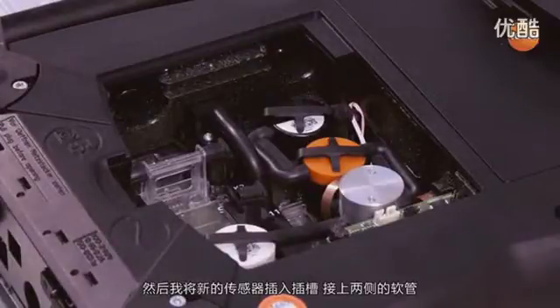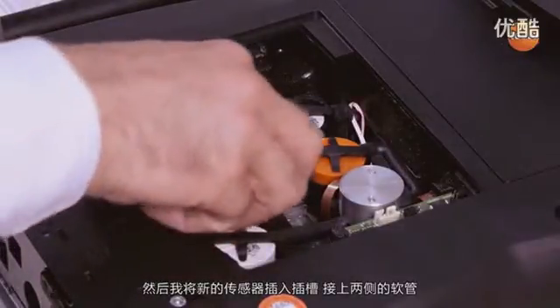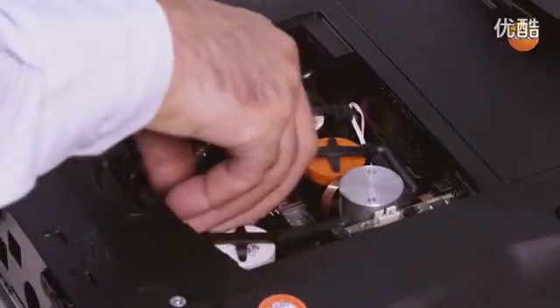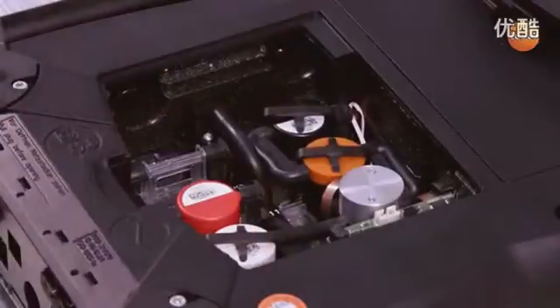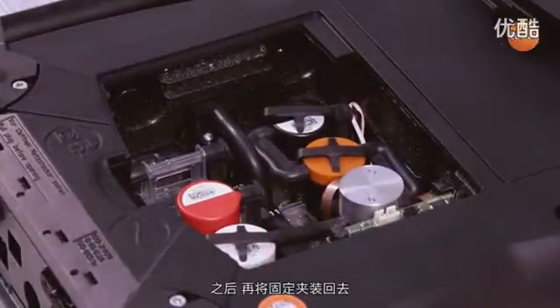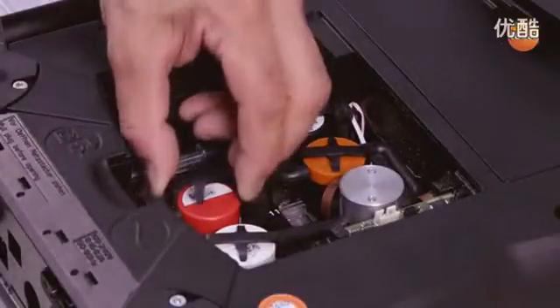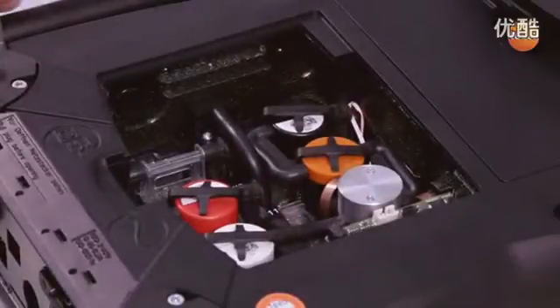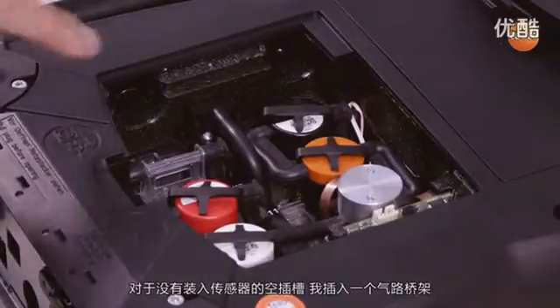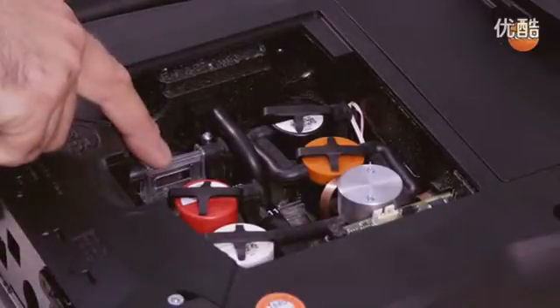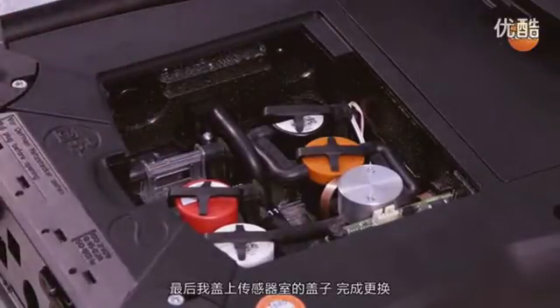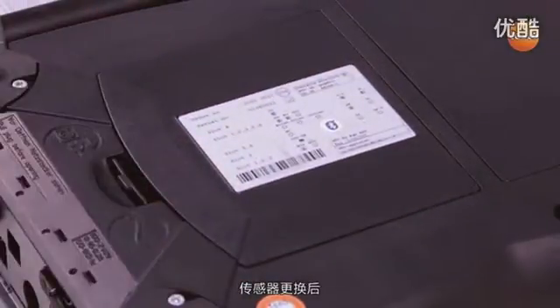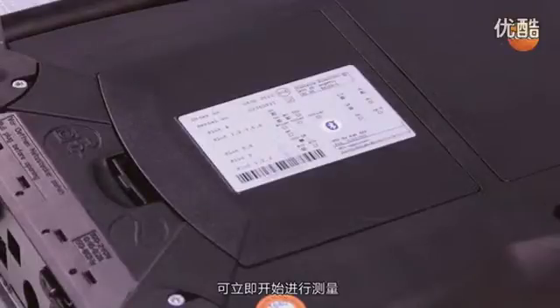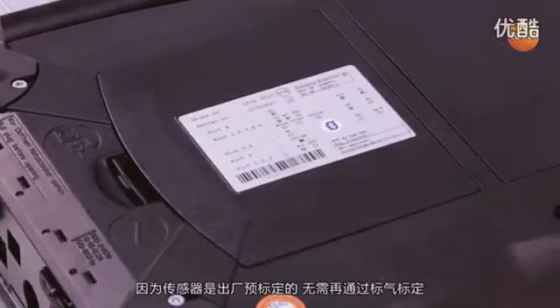I then insert the new sensor into the slot and connect the sensor to the hoses. After this, I click the clip back into place. I insert a slot bridge for slots which are not equipped with a sensor. Finally, I replace and close the sensor compartment cover. After replacing the sensor, a new measurement can be carried out immediately without adjusting the sensors with test gas, as the sensors are calibrated ex works.